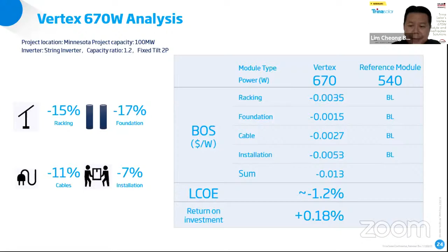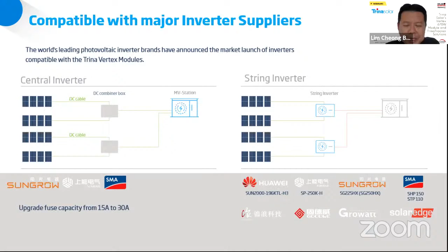We have also worked with various inverter companies because this is a high current module. On the left is a central inverter, so there's no problem matching with it, though there's a need to upgrade the fuse capacity from 15 amperes to 30 amperes to cater for the high current. On the right is a string inverter. We have worked with all the major inverter suppliers, and they have compatible inverter models that can match with these high current modules, already available in the market.